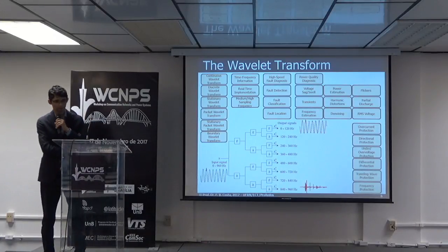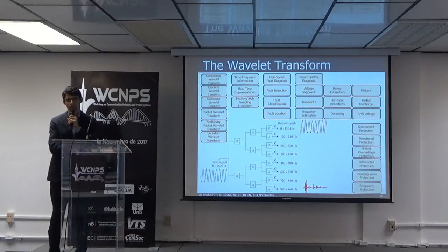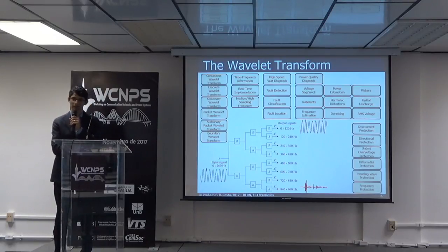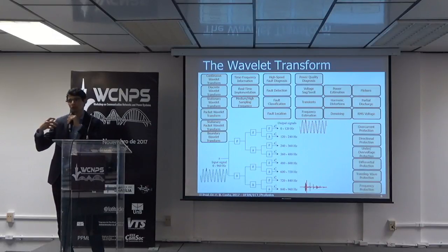And there are no technological problems by using a low sampling frequency in the order of 20 kilohertz, for instance. But by using a high sampling frequency, for instance, for the traveling waves, it's necessary to use, for instance, a current transformer with a high frequency response, and maybe if you need a very high sampling frequency, optical transducers could be used.